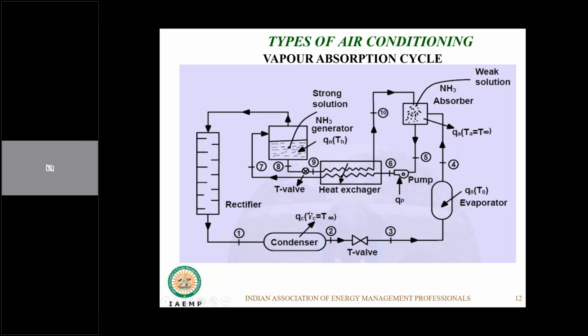Again, further cooling happens in the condenser through a cooling tower, where it comes close to its wet bulb temperature, and as it comes through the condenser, the liquid ammonia is then expanded in the evaporator, and the cycle continues. So the absorber cycle is over here. The water cycle happens between the generator and the absorber, and the ammonia cycle happens through the evaporator, absorber, generator, and condenser. So this is how the vapor absorption works on a broad scale.